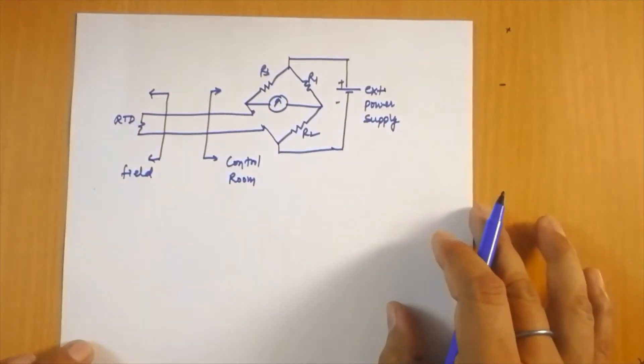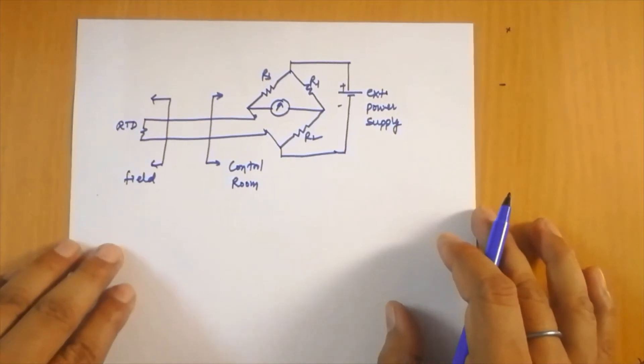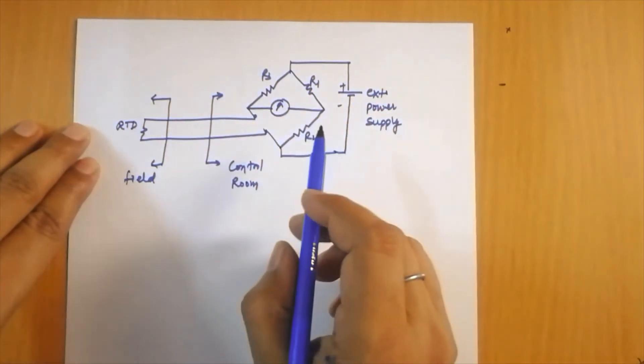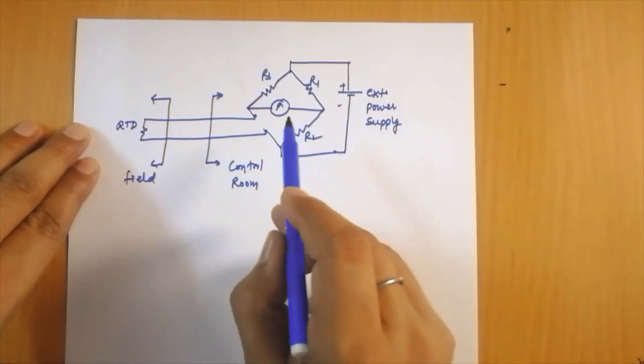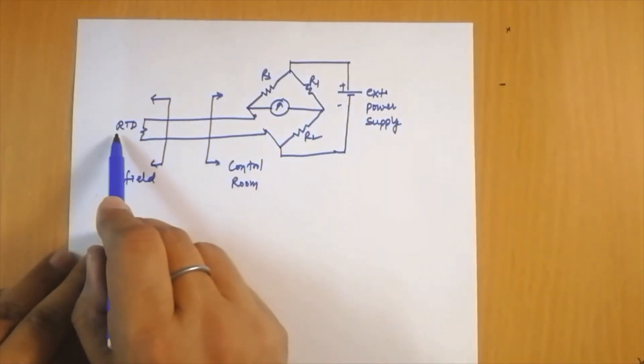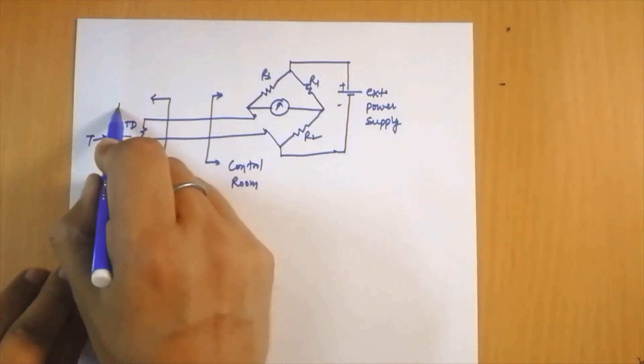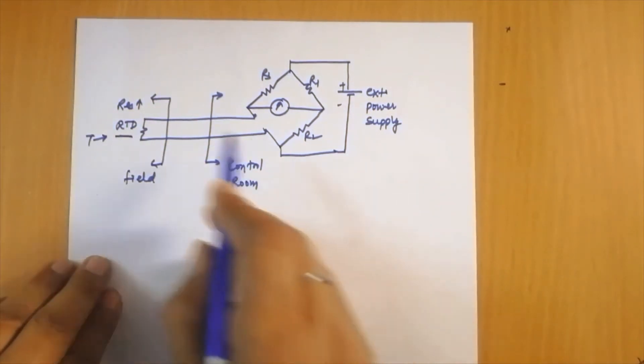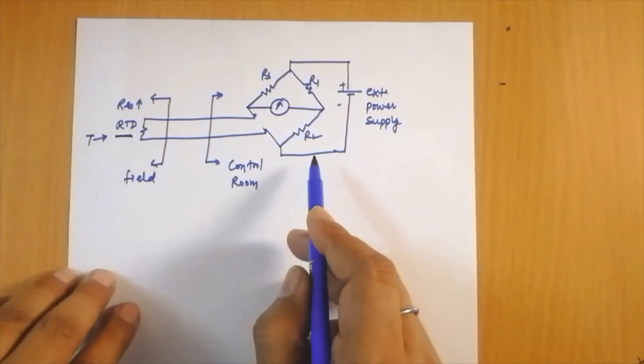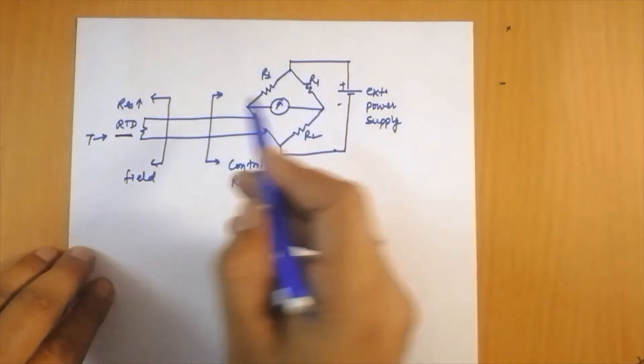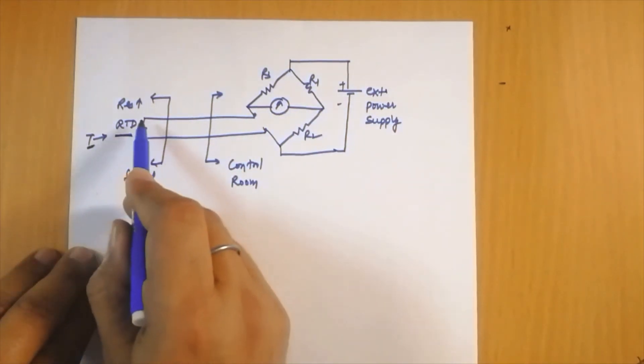Initially, when no temperature is applied to the RTD, the bridge is in balanced condition and there is null deflection in the galvanometer. Whenever temperature is applied to the RTD, the resistance changes — it increases with temperature in the case of a conductor. This changes the balanced condition of the bridge, resulting in deflection in the galvanometer. We can calibrate this meter to directly measure the temperature change that causes the change in resistance.